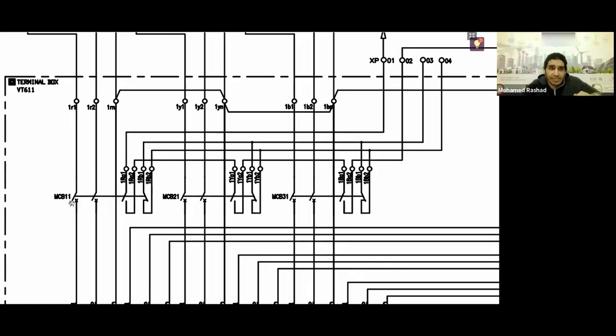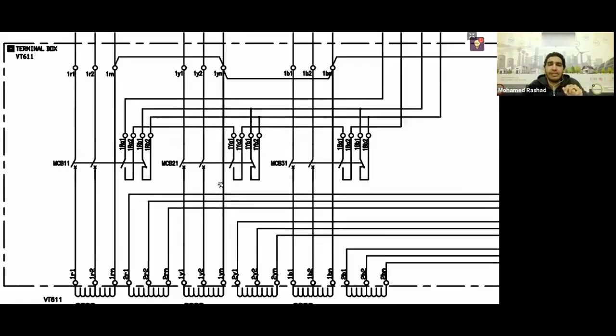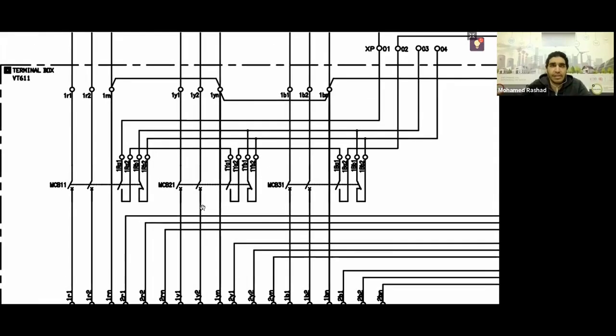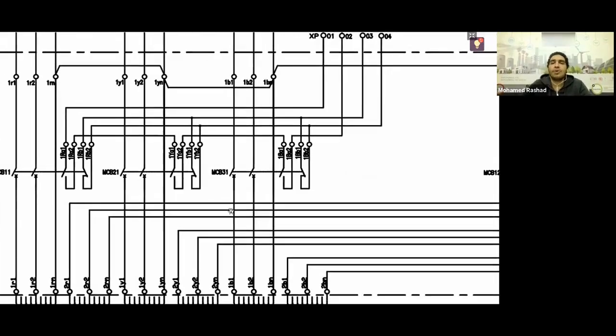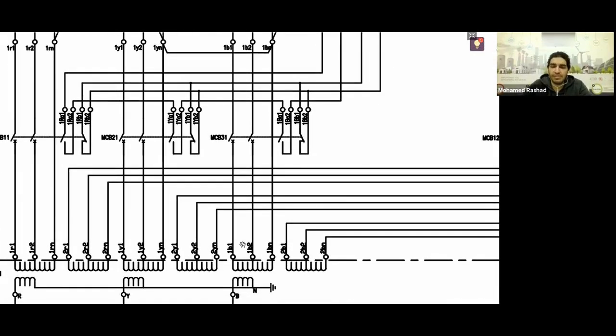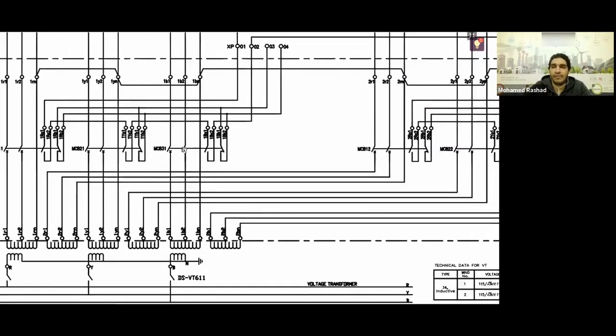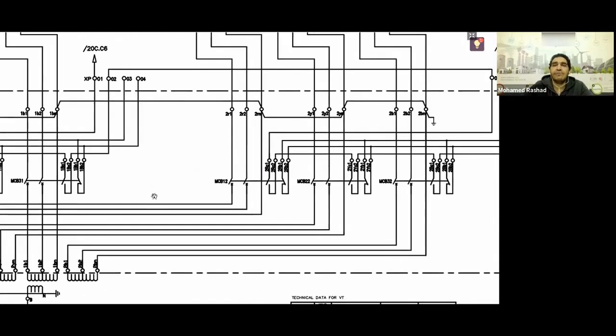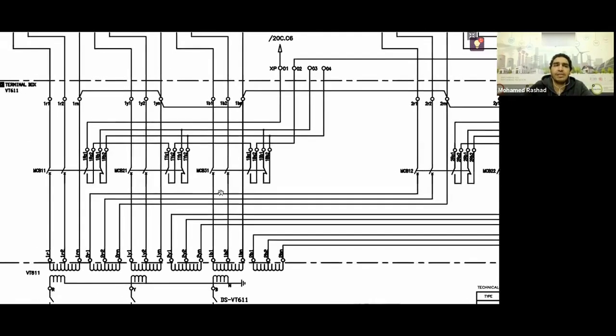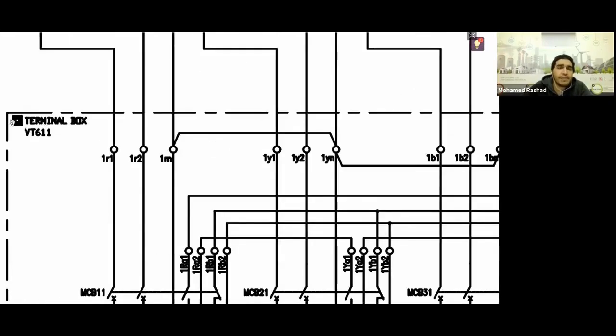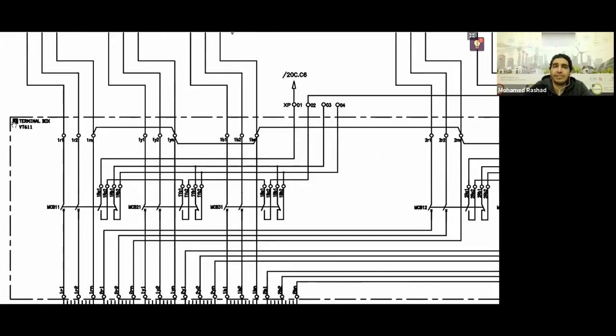If you close the MCB of phase A or phase red, this contact will close. And if you connect the MCB of the VT for the yellow phase, it will close. And if you connect the VT MCB of the blue phase, what happens to this contact? This contact will close. All right, great. So this is the set of MCBs present here. There's a box here, a black colored box. This means it's a mechanism box for the operation of the voltage transformer.